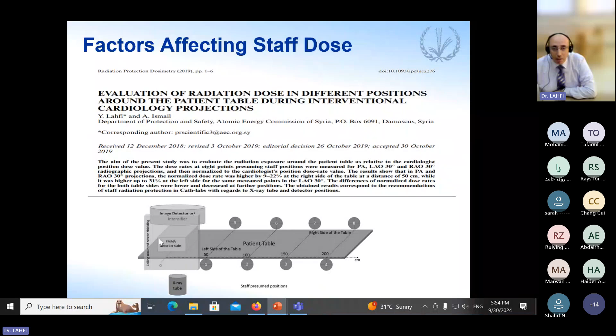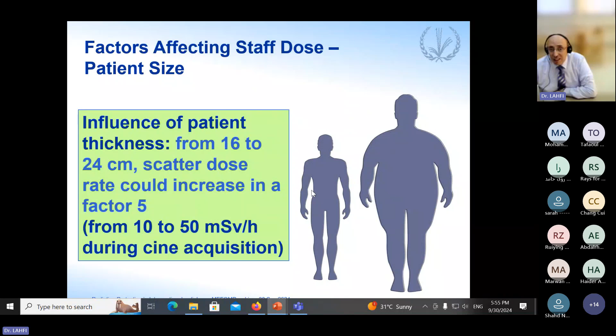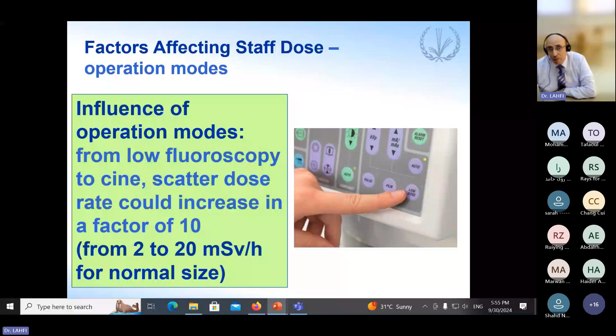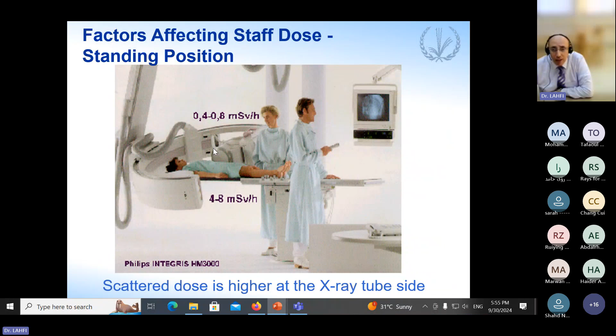One of the factors affecting staff doses is the patient size. It may lead to 10 to 50 millisievert during cine acquisition, as we go from 16 to 24. This is the patient thickness. Also, there is an influence of operation modes. From low fluoroscopy to cine, the scatter dose rate could increase by a factor of 10. It's from 2 to 20 millisievert per hour for normal size. Also, the standing position matters, whether we are on the X-ray tube side or the detector side. Scatter dose is higher at the X-ray tube side.